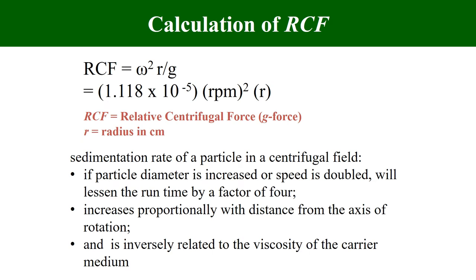Centrifugal force can be calculated using the formula G equals omega squared r. Another very important concept is relative centrifugal force (RCF), which relates centrifugal force to gravitational force: RCF = omega squared r divided by g, which simplifies to 1.118 × 10⁻⁵ × rpm² × rotor radius. The two factors that control sedimentation of any particle are the speed of the rotor and the radius of the rotor.